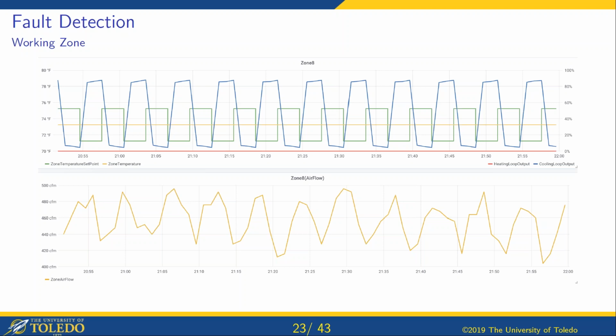Now this zone is working. You can see the airflow in the VAV changing in response to the cooling output loop here, which is responding exactly as we'd expect it to the changes we're putting through. One thing to take note of is the flat yellow line here - that's the actual temperature of this zone. We're not doing anything here which is affecting anything anyone's going to feel in the building.